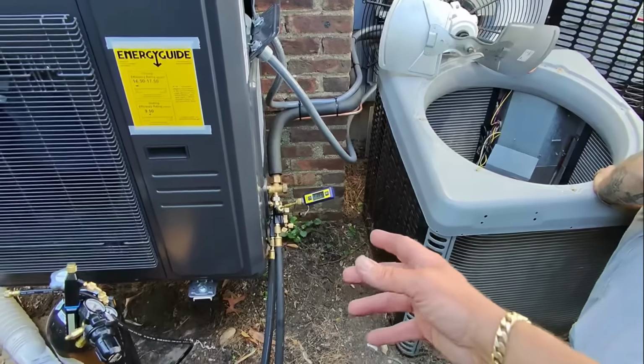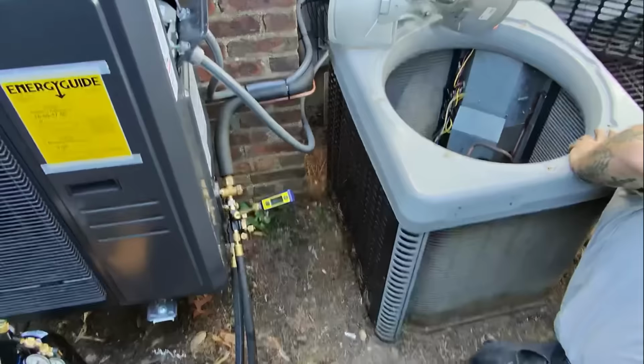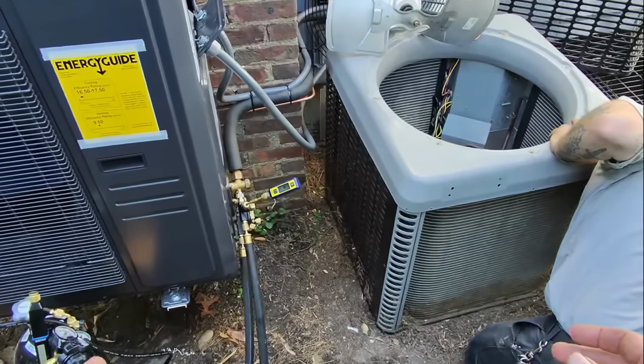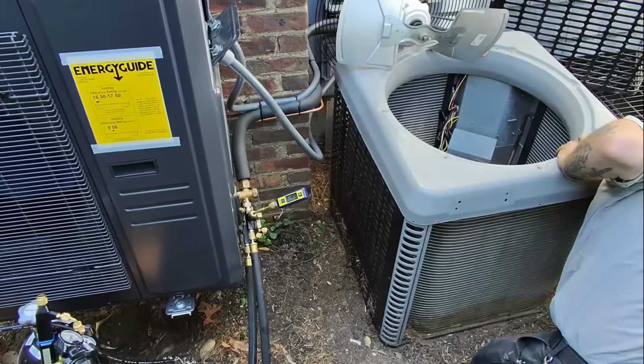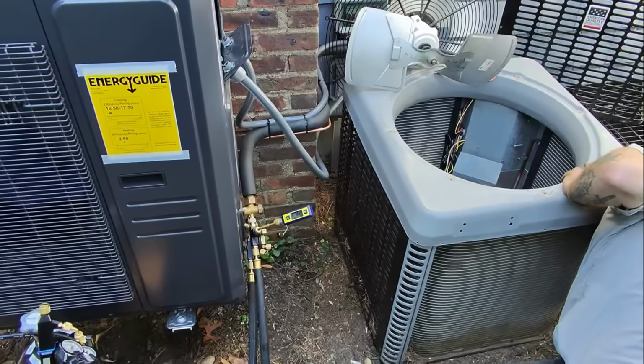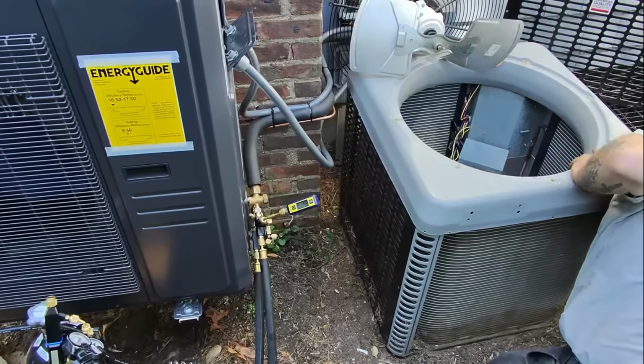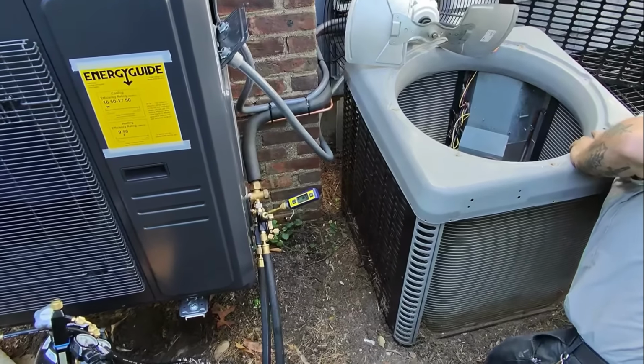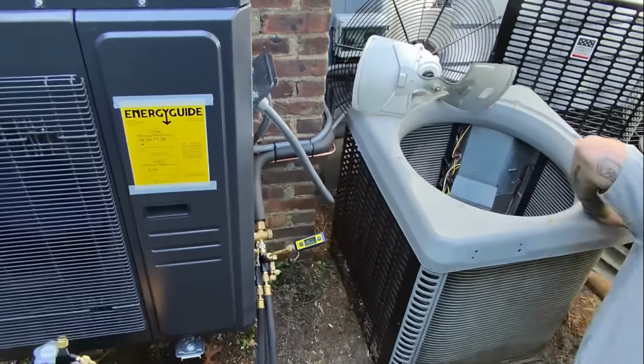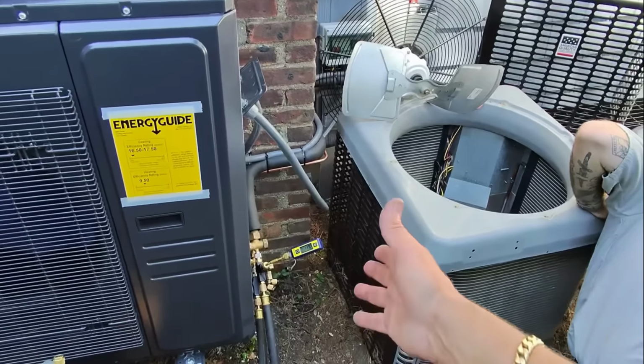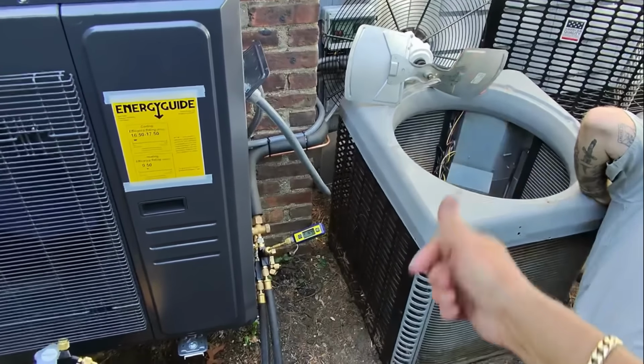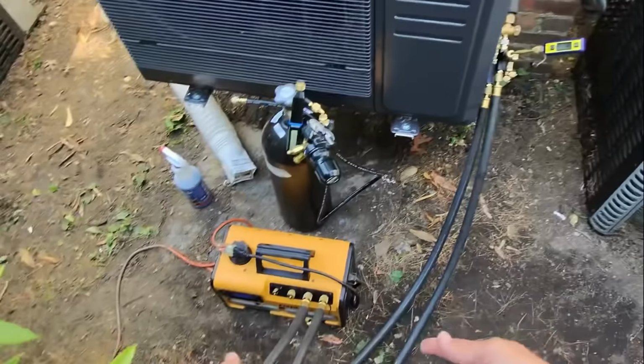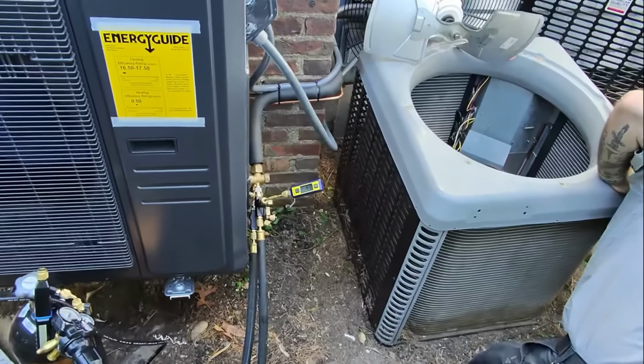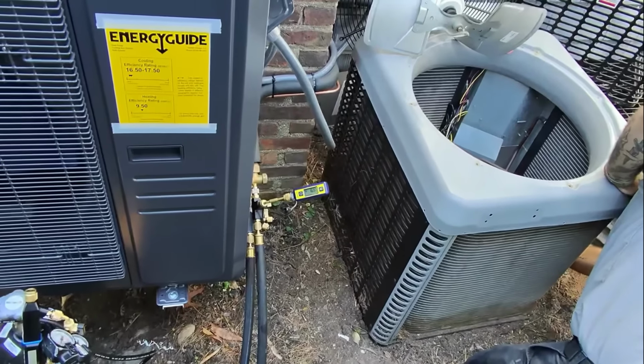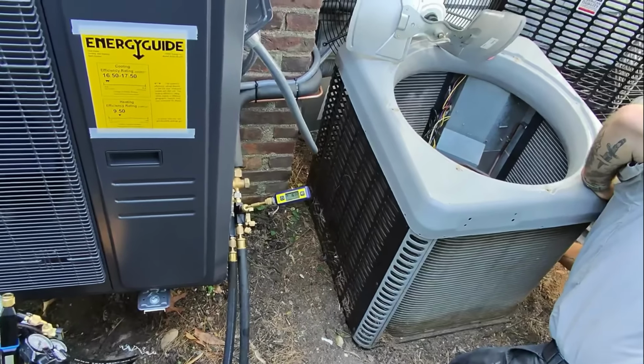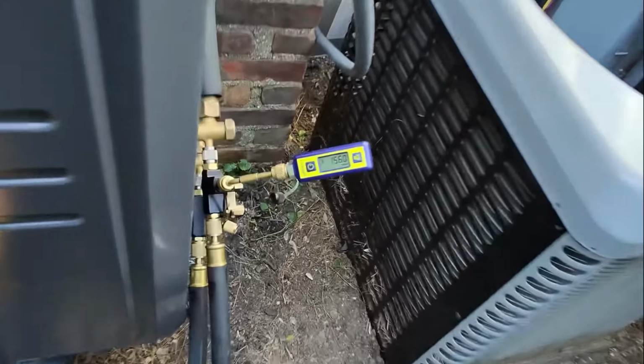So what's happening right now, folks, is that we're in a vacuum, so any moisture is going to boil off at room temperature as it's sucked down in pressure. And when it boils off, it's expanding around 14,000 times its mass. So you'll expect to see that jump up and then jump back down again because the vacuum pump is working. So we're at 1,500, 1,600, 1,700 microns. Slow and steady, folks.